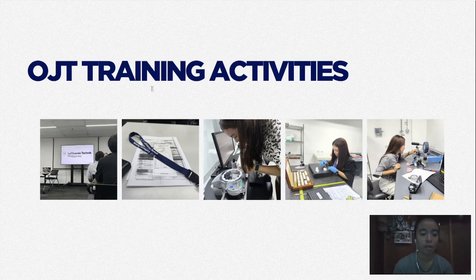I actively participated in dimensional calibration routines using high-grade ceramic and steel master gauge blocks. So kinalibrate namin yung outside micrometer here. As you can see in this picture, I verified measuring anvil flatness and parallelism, inspected the spindle pitch to detect mechanical lead screw wear, and adjusted the zero point baseline to maintain sub-millimeter and micro-inch tolerance critical for sheet metal and rivet inspections.